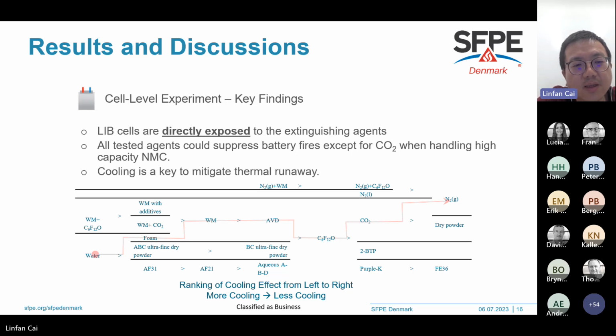To mitigate thermal runaway, the cooling effect of the extinguishing agent is very important. From the more than 20 different extinguishing agents, I ranked their cooling effects from high to low, left to right, in this table. For example, water is more effective than foam, foam is more effective than water mist, then AVD, then NOVEC and inert gases, in that sequence, and likewise for other combinations. Overall, water-based agents are the most effective in cooling, and cooling is the key factor to mitigate thermal runaway at the cell level.